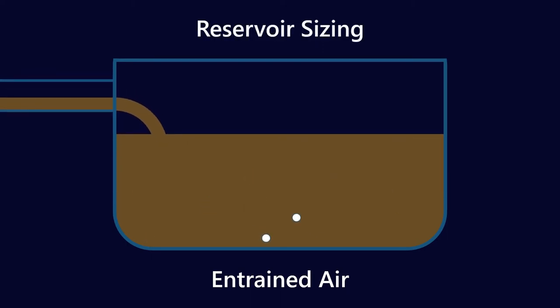Now let's talk a little bit about the reservoir sizing because realistically what we want is the way that we get rid of entrained air is that bubbles naturally are going to want to rise to the surface where, if the surface tension is low enough, they'll pop. That releases air into the system. So that's what you want. You actually want entrained air to rise up, get to the top, form foam, but a very unstable foam that is going to dissipate very quickly.